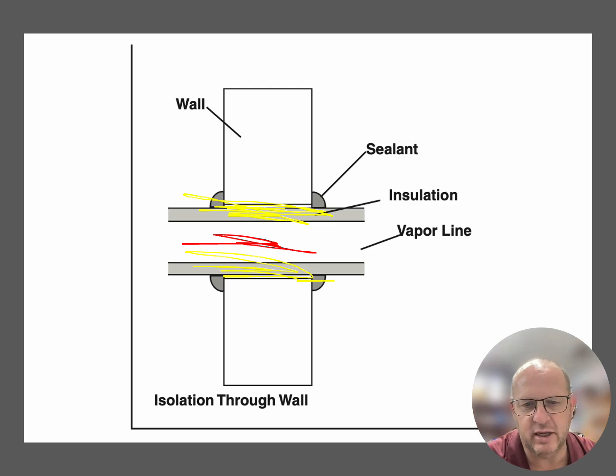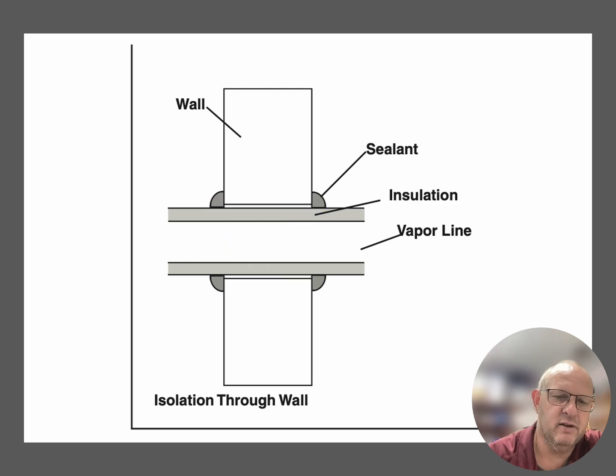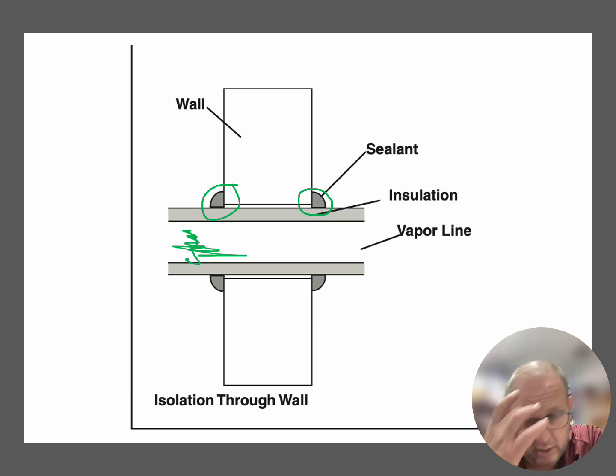It's also going to give me a nice area to seal up around, and then I want to fill up that cavity that I'm running my liquid line, my control voltage, and possibly my high voltage out through that hole. It's going to allow me a nice area to put a sealant on that pipe as it's coming through. I'm going to want to fill this cavity as well, after the installation, after everything's okay, so we don't get any air coming into the house or the environment that way.